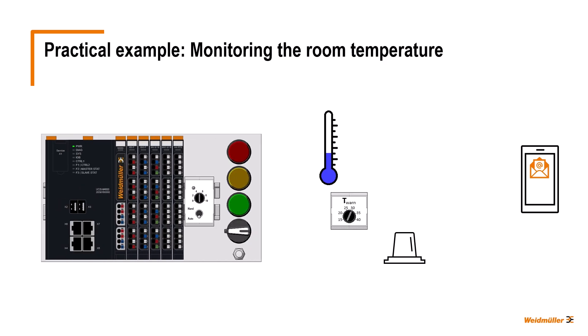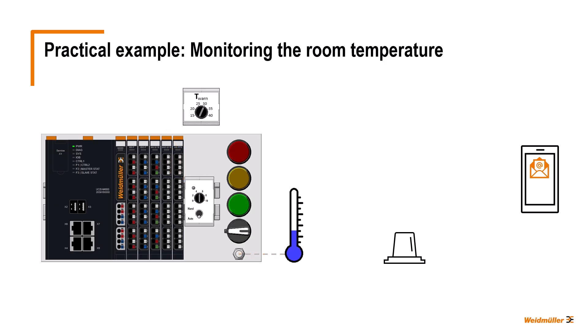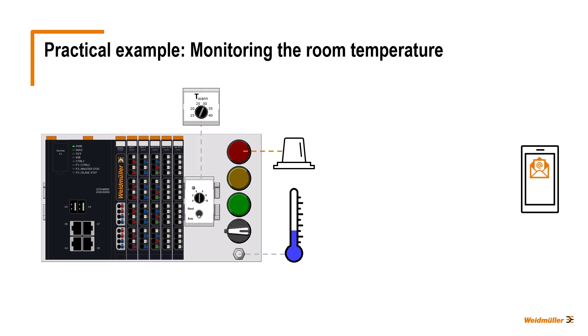We now want to implement this with our U-Control starter kit. For this we use the following elements: We will use the PT100 temperature sensor to measure the room temperature. This sensor is connected to the temperature measurement module on channel 0. We use the potentiometer connected to the analog input module on channel 0 as the rotary switch for setting the temperature limit value. And the red light of the starter kit, which is controlled by channel 0 of the digital output module, acts as the alarm light.